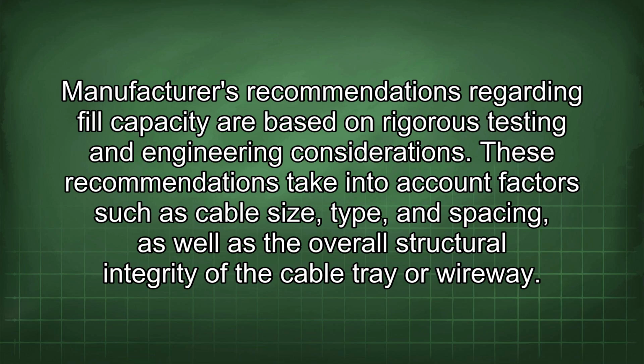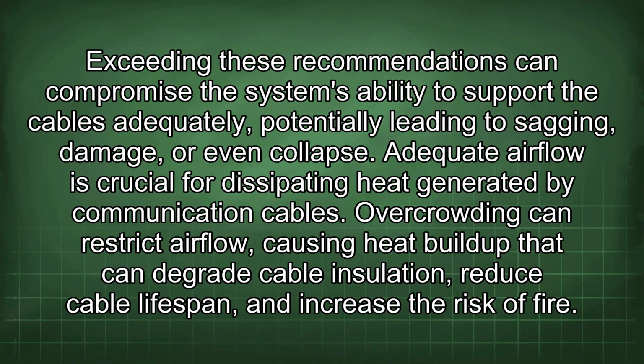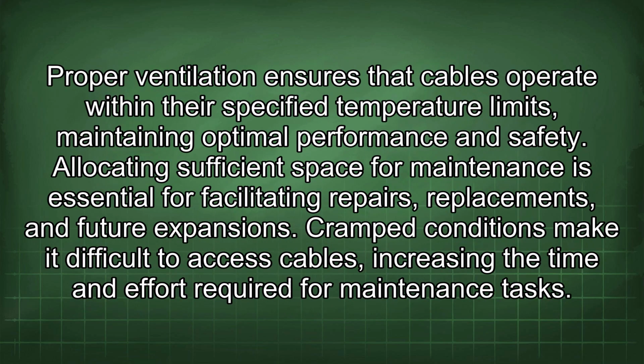These recommendations take into account factors such as cable size, type, and spacing, as well as the overall structural integrity of the cable tray or wireway. Exceeding these recommendations can compromise the system's ability to support the cables adequately, potentially leading to sagging, damage, or even collapse. Adequate airflow is crucial for dissipating heat generated by communication cables. Overcrowding can restrict airflow, causing heat buildup that can degrade cable insulation, reduce cable lifespan, and increase the risk of fire. Proper ventilation ensures that cables operate within their specified temperature limits, maintaining optimal performance and safety.